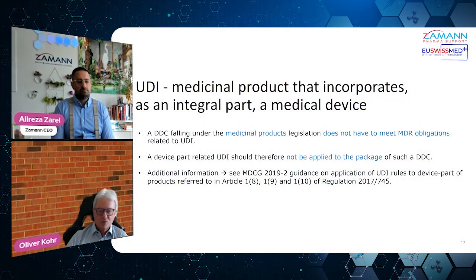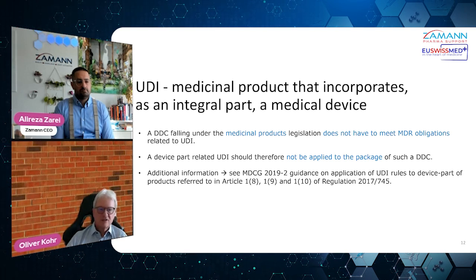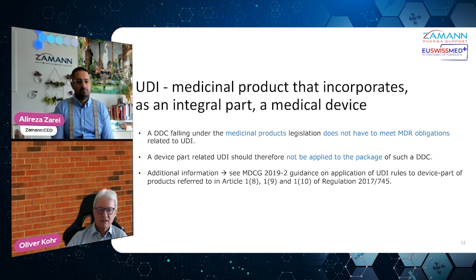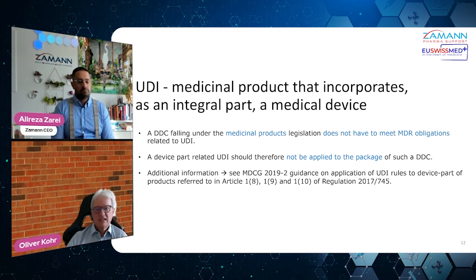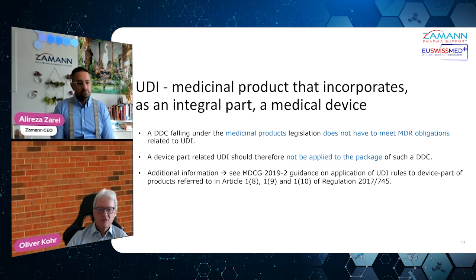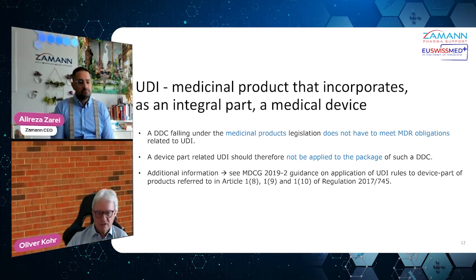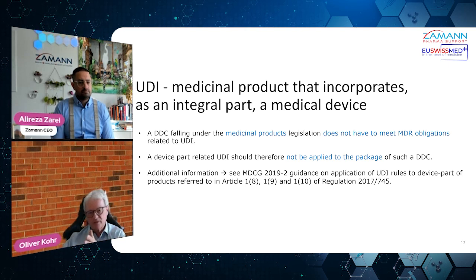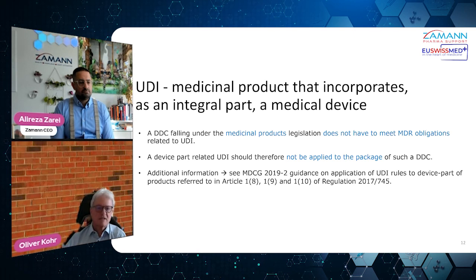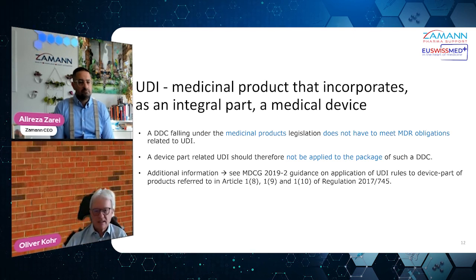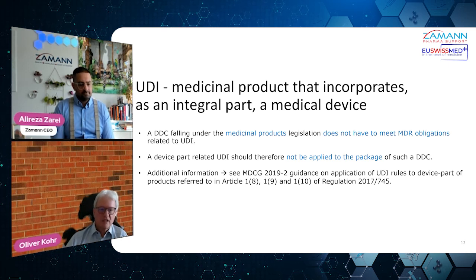UDI, now it comes more to labeling. If the DDC falls under medicinal products legislation, then you do not need to meet the MDR obligations related to the UDI. That's because you need the UDI, and of course the Eudamed database, medical devices, Eudamed, and all these kind of things. So this then gets, so to speak, eliminated. You don't need to have that.